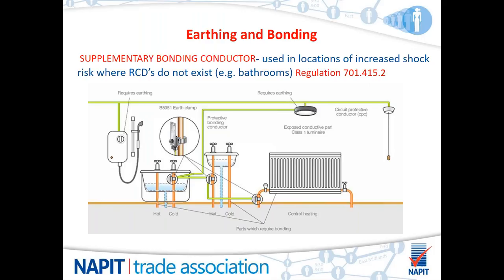These are used primarily in places where there is increased risk of shock and RCDs do not exist, e.g. older installation bathrooms. Supplementary bonding, according to the regulations, and regulation 701.415.2 says that it should be in place, and then it sort of contradicts itself and turns around and says may be omitted if, and there are three ifs and they all need to be there: if the main bonding is present to water, gas, oil, etc., if the pipework is of a continuous piece, and if there is an RCD fitted to all low voltage circuits within the location, then supplementary bonding isn't, as I say, required.